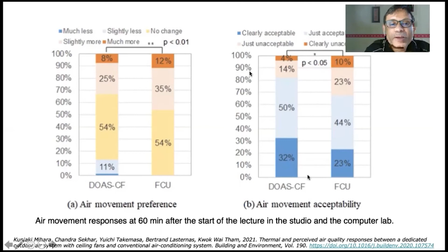Indoor air quality acceptability and dry eye discomfort at 60 minutes after the start. Again, we find the DOAS-CF and the FCU are both equally good, and I've already given you the reason why. In both situations, we are indeed ensuring the right amount of ventilation. In fact, the DOAS-CF is even better because it's 100% outside air. In the FCU there is an element of recirculation involved, but it's still providing the right or required amount of ventilation.